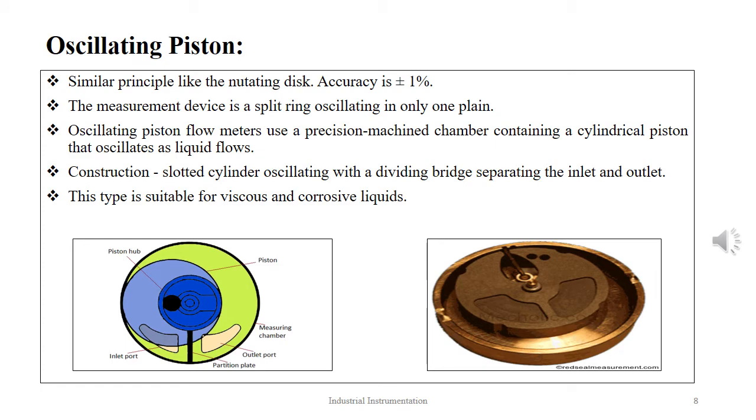The second type of positive displacement flow meter is the oscillating piston. The oscillating piston flow meter uses a precision-machined chamber containing a cylindrical piston that oscillates as liquid flows. The piston's central shaft is constrained to run in a circular groove in the chamber, resulting in an off-center rotating motion as the liquid sequentially enters and exits compartments machined into the underside of the piston.